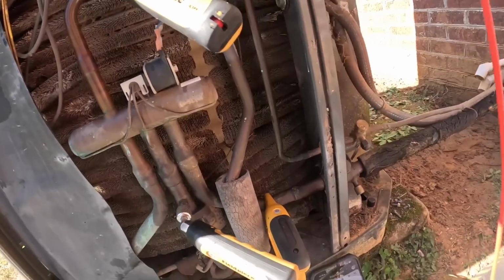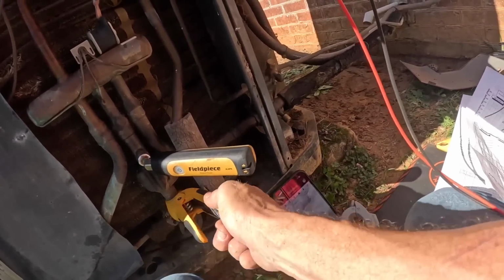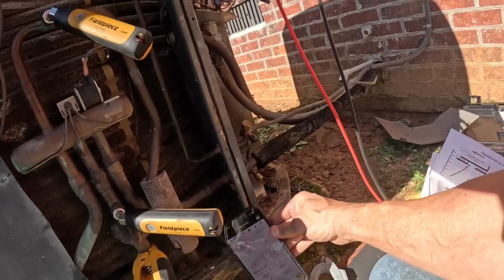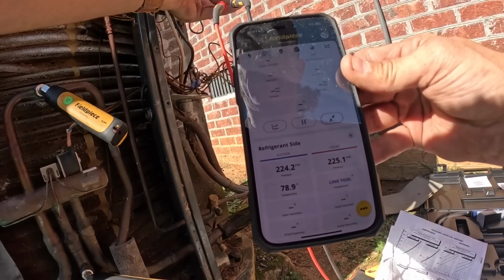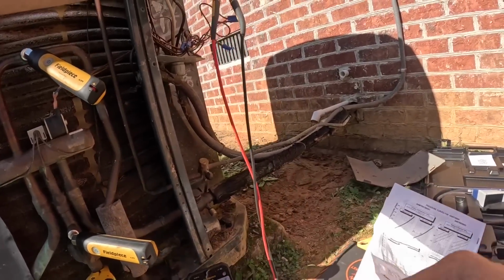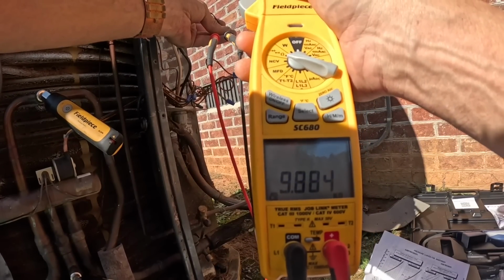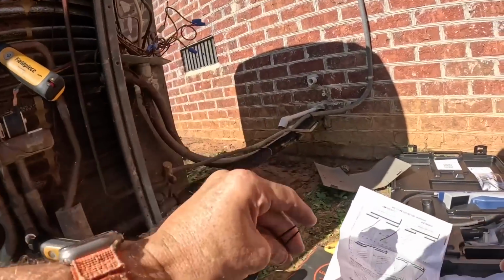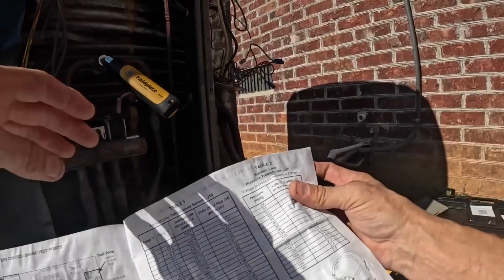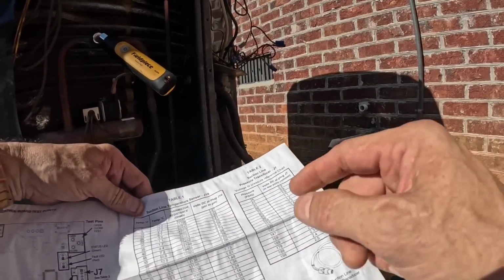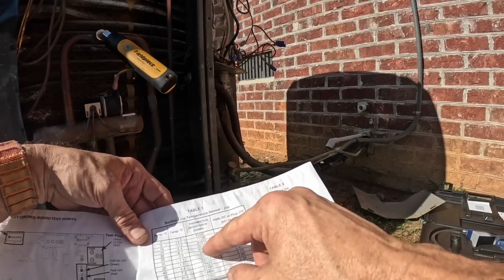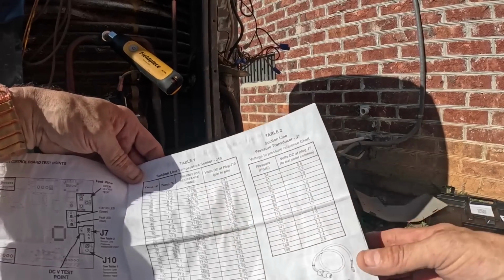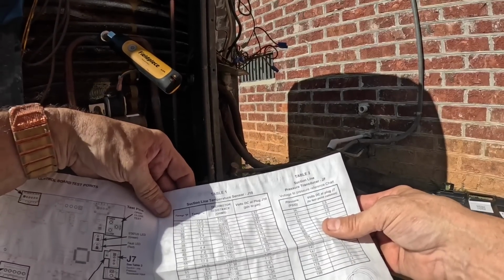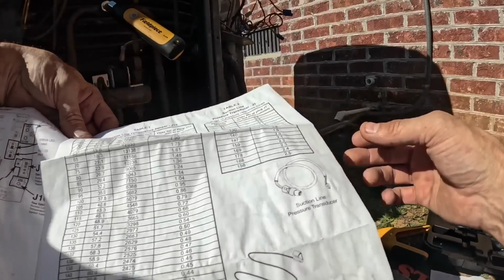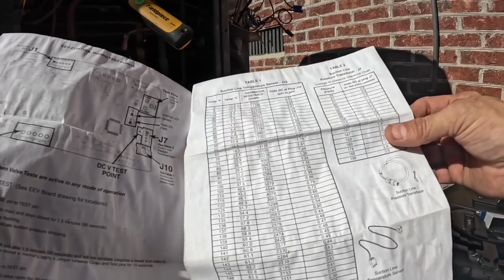We're testing our suction line temperature sensor. I really should have this right beside it. I've got 82 degrees, 78. I was reading 77 on the other side. Right at 9.9 thousand ohms. That ain't even on the chart. Thermistor resistance, suction line temperature sensor J10.